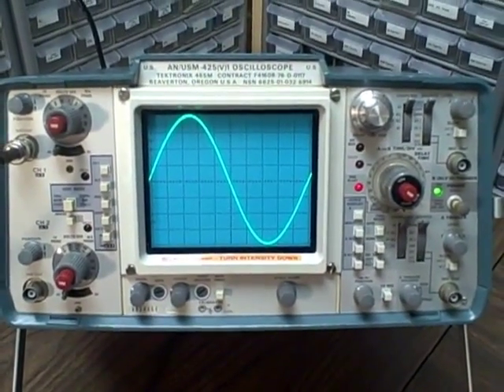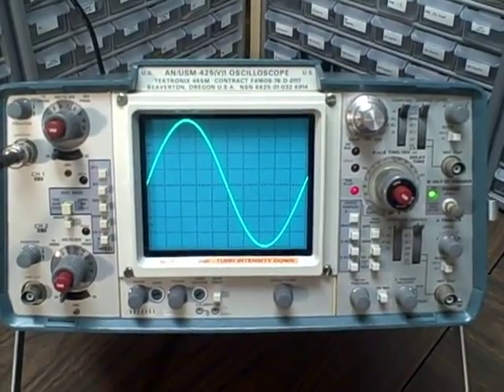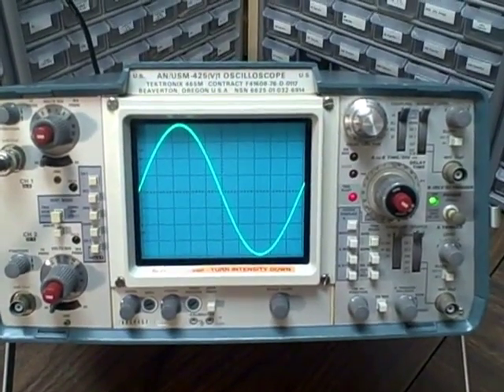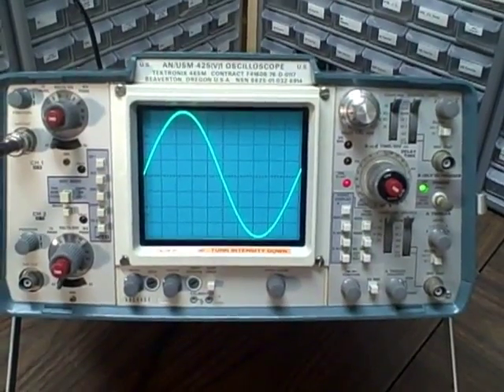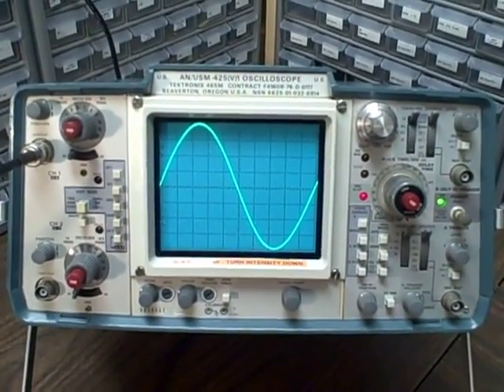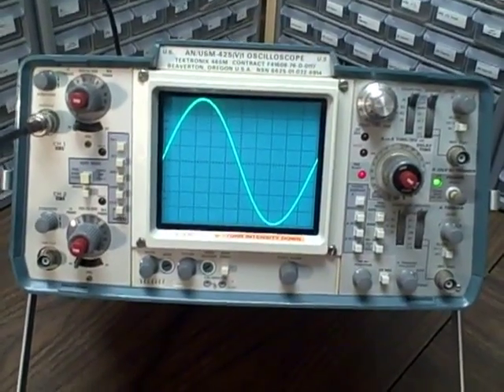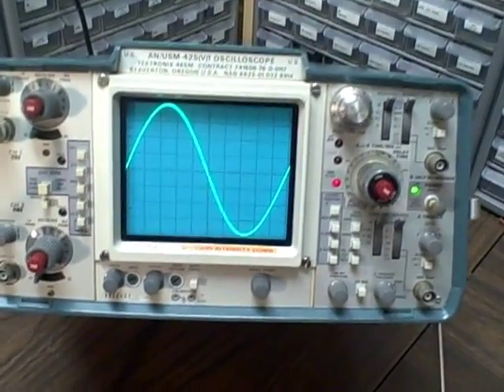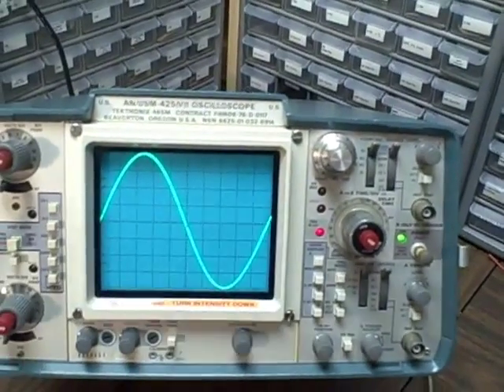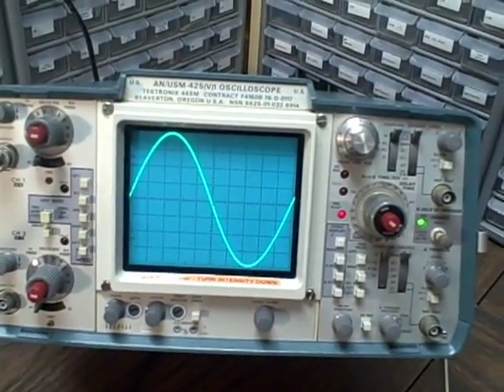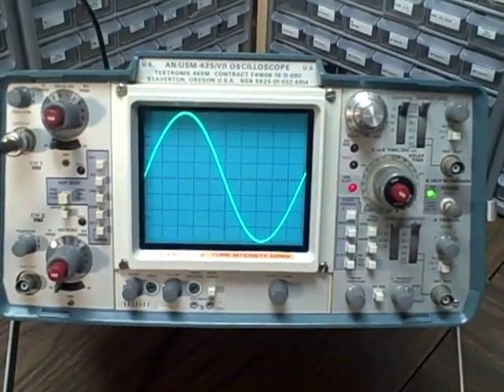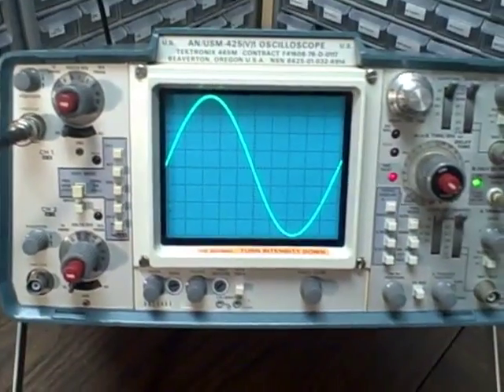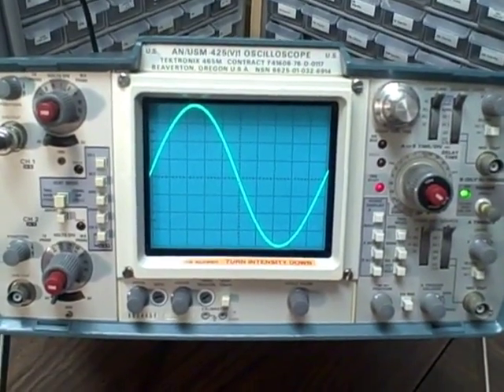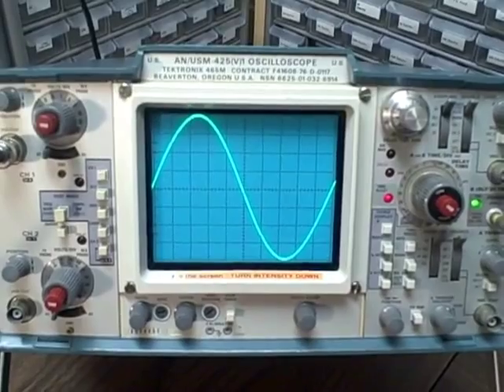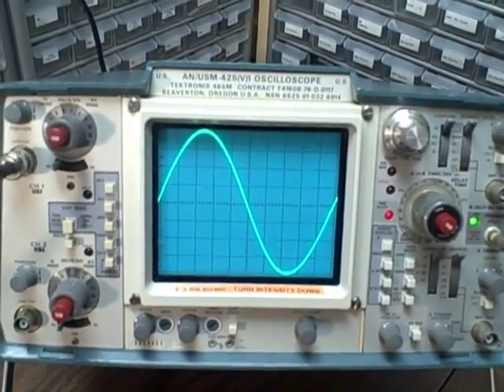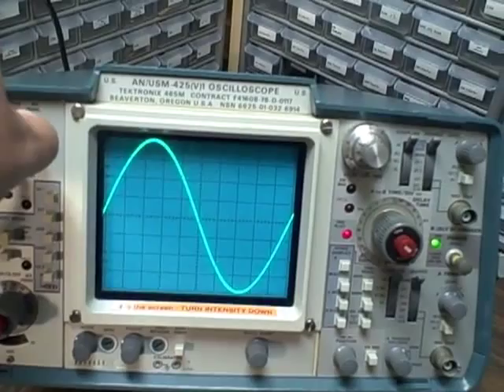The 465 will measure frequencies from DC to beyond 100 megahertz at its 3 dB point. We'll test that on this unit and show that she's still in cal and that she's capable of achieving that bandwidth. It has a limiter switch that'll also reduce the frequency response to 20 megahertz to eliminate effects of high frequency when you're looking at mid-range. She'll read 5 millivolts per division to 5 volts per division, and she'll do it in 10 range steps using the vertical range switches.